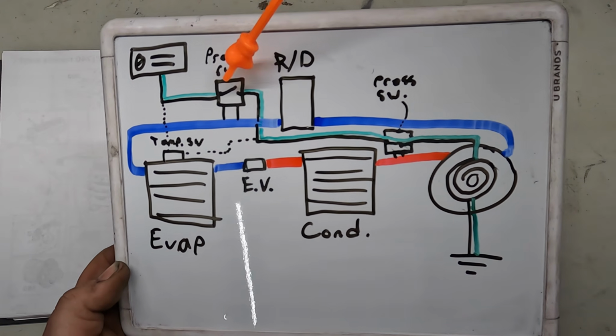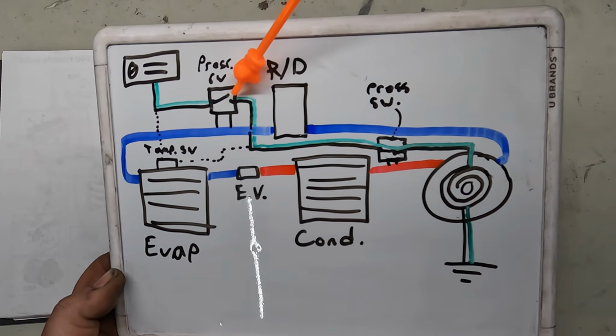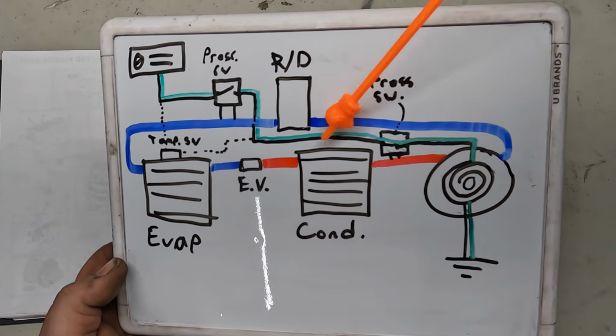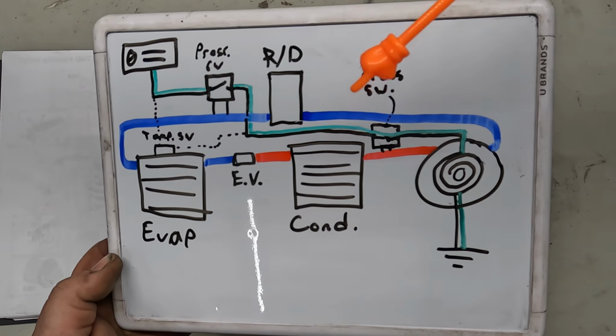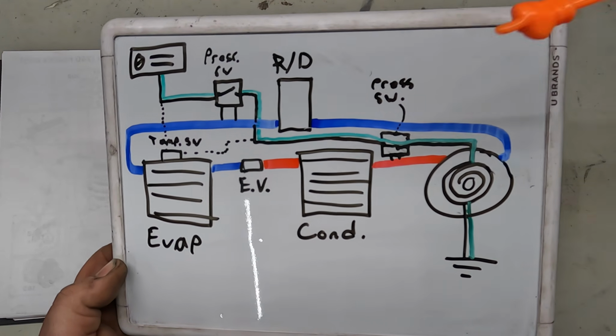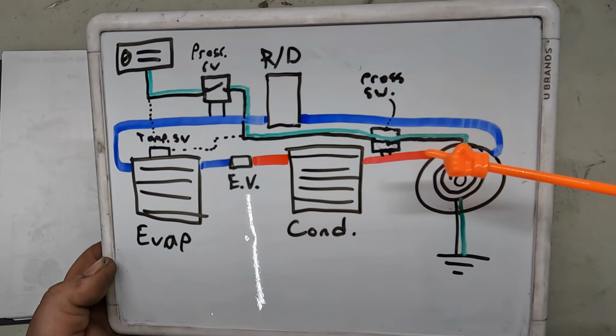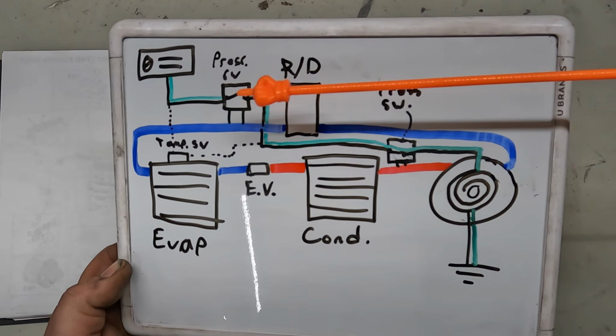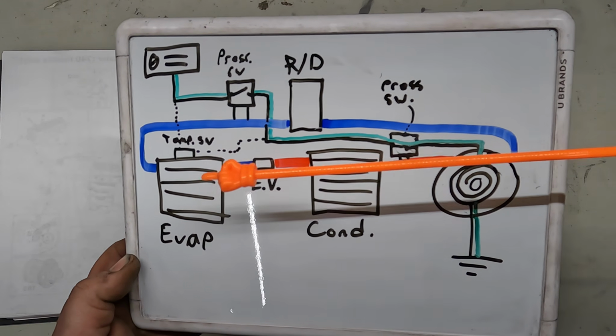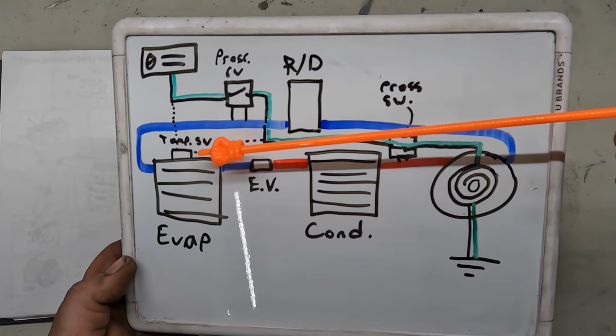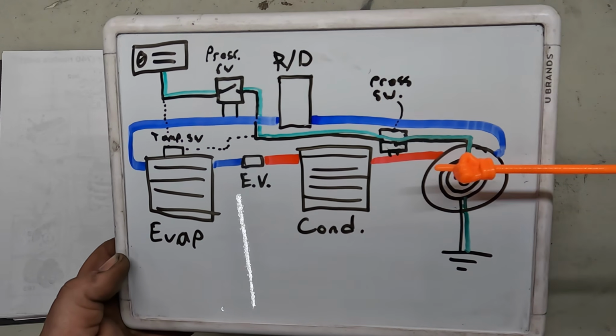So to prevent the compressor from running when the system is empty, we'll have a low pressure switch here, and in series with it will be a high-end pressure switch to cut the compressor off if pressure gets too high on the high side. Instead of either of these switches, or along with one of them, we might have a temp switch on the evaporator, in case it gets too cold, to cut the compressor off.